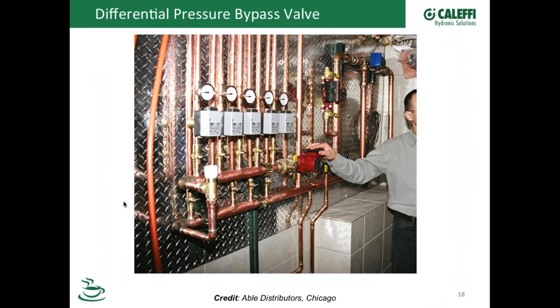And here's a classic example of a job that has the bypass valve in it there, and there's the pump and multiple zone valves. A couple different ways you can set up this valve. I know some of the valves out there, there's numbers on them, and there's a table in there, and if you look up what size pump you have, it might tell you the number to set it on. The threshold pressure, the cracking pressure is what you want to adjust on that. So when all the zone valves are open and it's flowing, you could actually put your hand here and you shouldn't feel any of the temperature. Let's say this is running at 180 degrees. You won't feel any warmth, any temperature here, because the valve is completely closed down.